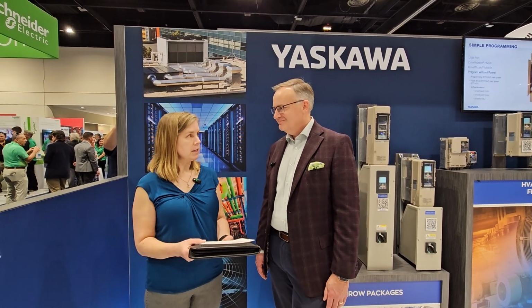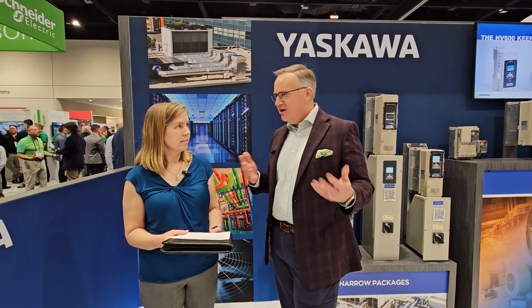What are the reasons for and benefits of using VFDs in today's HVAC equipment, like air handling units or heat pumps? Yeah, I mean, VFDs are really important. If you look at most applications, you're usually going to run at part load conditions. You're not going to run at full speed all the time. Most buildings you're going to design for 95 degrees or 100 degrees, just depends where you live. But most of the time, it's not going to be that hot. You've got so much capacity you're designing for, but it's not going to be that hot all the time. So you're going to run at lower conditions a lot of the time.